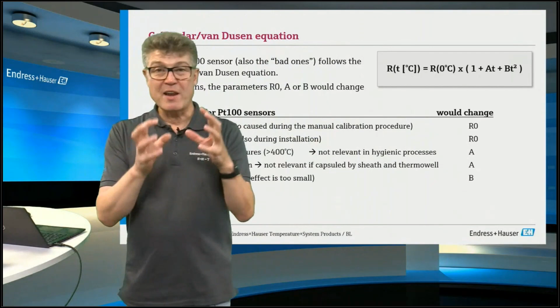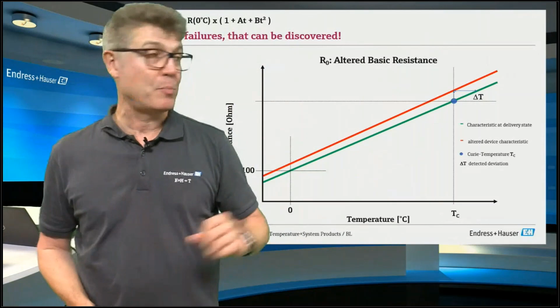So that means the main factors which are a real risk in your application are mechanical shock and thermal shock. And they can be easily seen because if this would happen, the curve is looking like this. If this would happen, the green curve becomes the red curve. We do the calibration at the Curie temperature. We will see a difference. This difference is not totally constant, but big and in the entire measuring range. That means if we identify a sensor to be bad at the Curie point, it's bad at the process temperature.